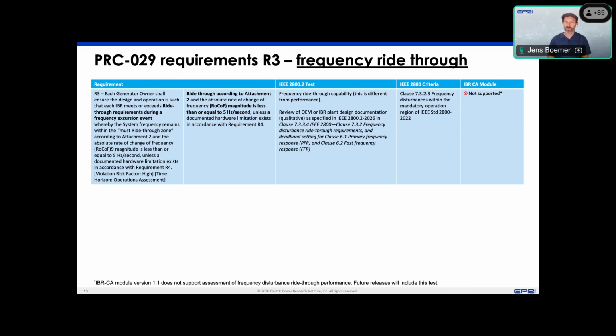deviations. But it's important to highlight that .2 decided not to include tests that test the frequency ride-through capability all the way up to the edges of the frequency ride-through curve. This is actually done by a review of the IBR plant design documentation and OEM unit documentation. So therefore, this requirement is not supported by the EPRI IBR CA module at this point, but it is something that future releases can still include as industry may consider a need for that.